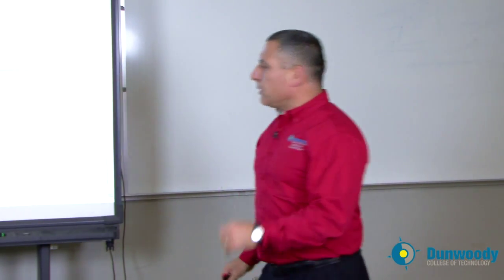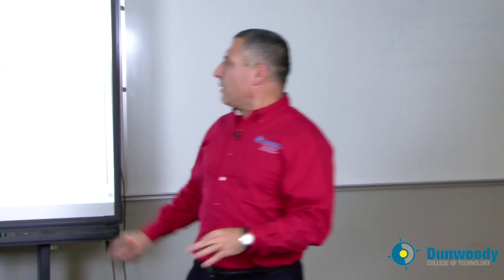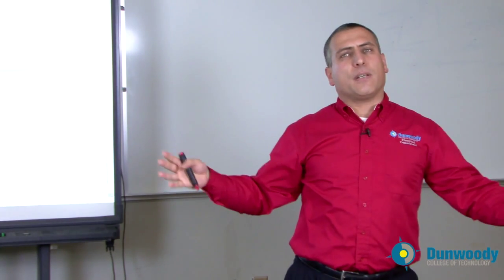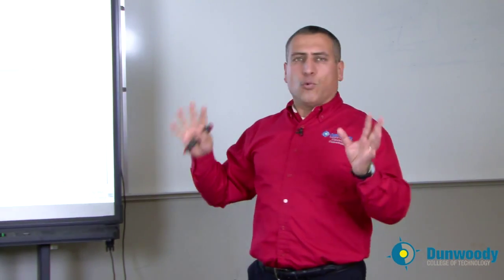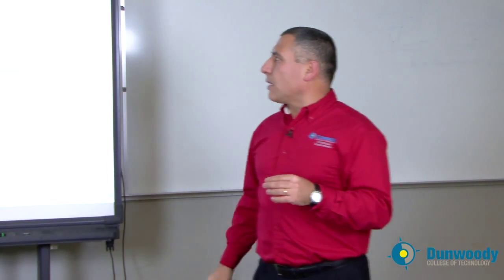Very important topics in special conditions to pay attention to is emergency systems. Every building needs an emergency system. Here's my emergency system: the wiring methods, the power source, separating emergency lights from other lights, everything related to wiring them and powering them — right into Article 700.